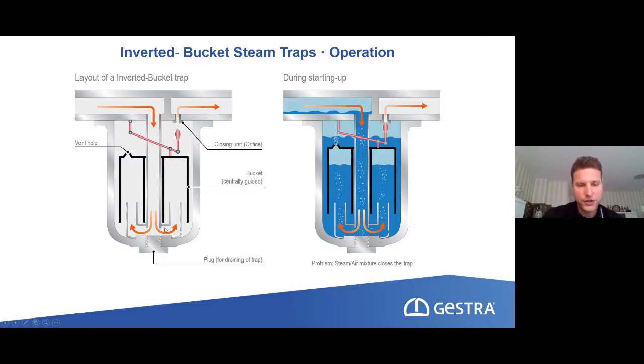So if the condensate travels through here, it will just go this way, and then it can be discharged via this closing unit into the condensate line. And as soon as we have steam appearing, then this little bucket will be lifted up, and then we have the connections here, and the plug will be pushed inside the orifice, and then the steam trap is closed.